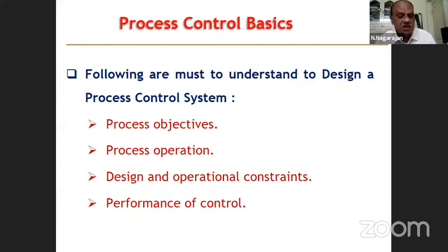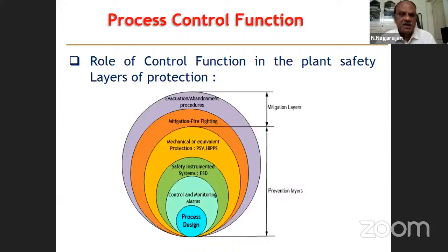Performance control means you have to get the required performance, run the equipment at the desired capacity and efficiency levels, and energy is another important thing. You have to manage the energy utilized in the process effectively, and no wastage of energy is advisable. So for process control functions, I am showing you both process control as well as the safety functions. The control system in a process plant has two layers. One is called the control layer. Another one is the safety layer. Both are independent layers, so you should be very clear that we are not linking the layers.